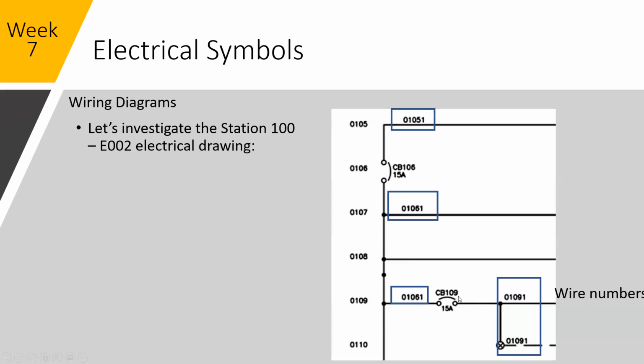The wire numbers increment up when you cross over to another device, when you move into a different panel. That's when you would change the wire number, because like we saw with the single line drawing, this 120 volts coming out of this circuit breaker is supplying power to all of these different devices. On here on 0108, there could be a light over on the other side, or there could be a control relay. We wouldn't increment up the wire number until you got to the other side of it. Are there any questions about that? Does that make sense? Does that not make sense to anybody?